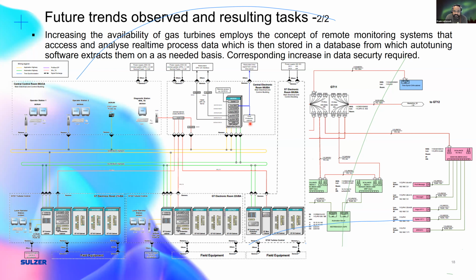We process the data so we can give recommendations to the client, telling them, based on your combustion dynamics, we've realized your gas quality has changed - can you please verify that? If the client says everything is okay with the gas supplier and gas chromatography, we may need to introduce a tuning session where we come on site to fine-tune the machine to run safely based on current gas characteristics. Or there could be weather changes - it gets cold or hot, and you move out of your optimal zone, requiring an external tuning session.